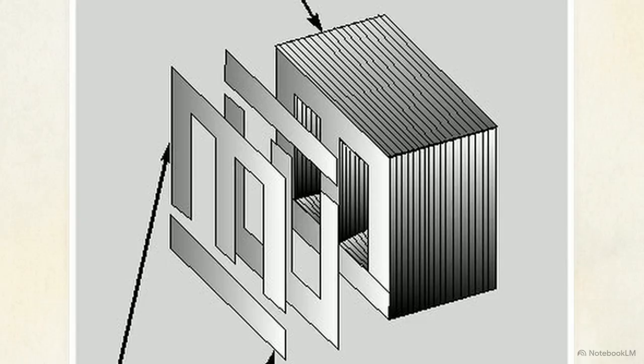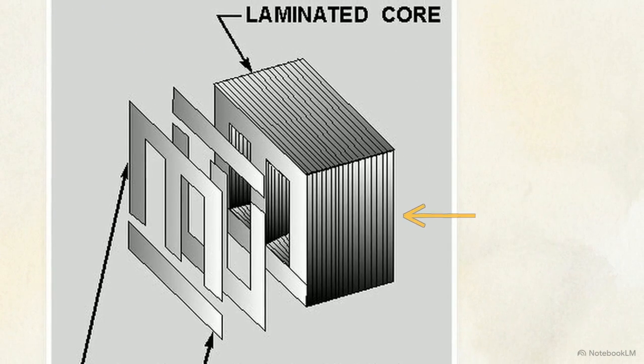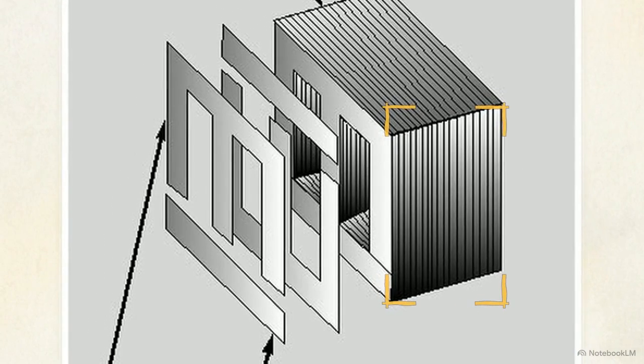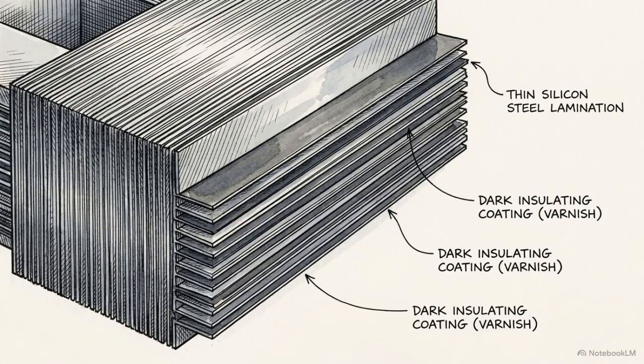Look closely at this diagram showing how engineers solved this. The core is not a solid block of iron. It is actually built out of hundreds of paper-thin steel laminations. Every single slice is coated to electrically isolate it from its neighbor. This creates microscopic physical roadblocks that stop wide eddy currents from forming, trapping the heat and keeping the system running at near-perfect efficiency. To defeat the parasitic physical forces that would otherwise destroy it from the inside out, the core has to be meticulously sliced, coated, and reassembled.